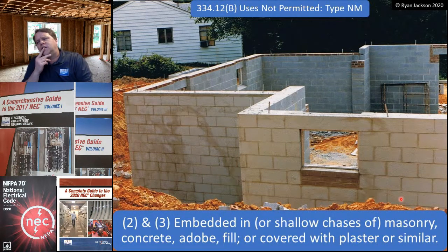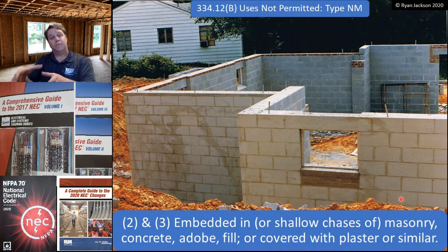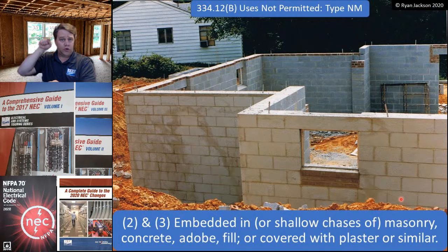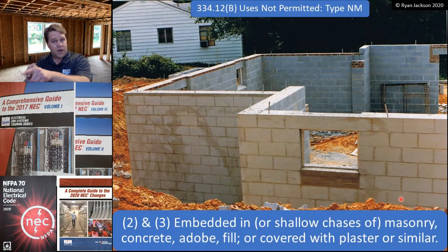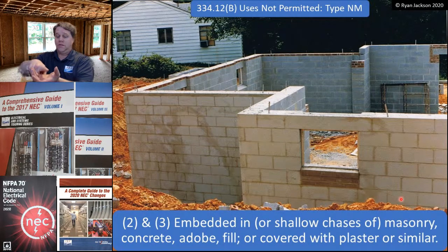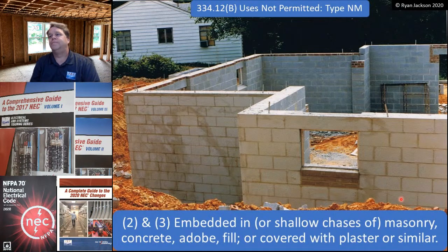I've had a lot of inspectors misunderstand or misapply this requirement. It's very common, at least in my area, down in a basement of a house. You'll have the exterior foundation wall, and then beneath the front porch, you'll have a cold storage room. Very common indeed to hammer drill a hole through that wall and run some NM cable into the cold storage room for a light. Now, that is not embedded in concrete. Embedded in concrete is when I put it in the form and then pour concrete around it. So drilling a hole through the concrete and running the cable through it is not embedding it in concrete or similar. So that would still be okay.